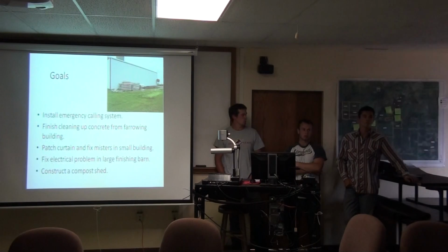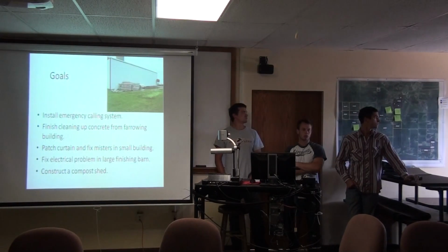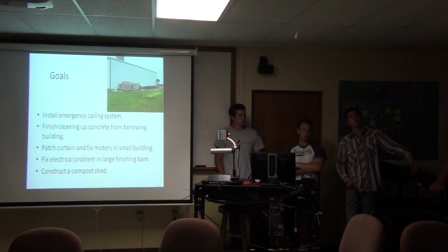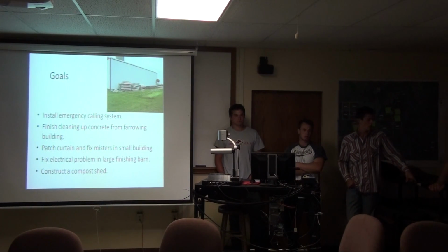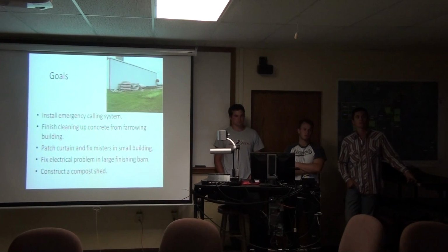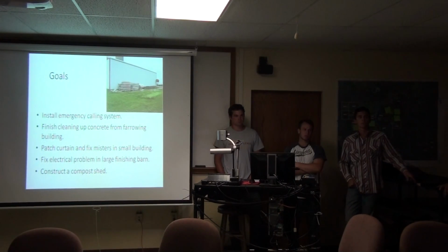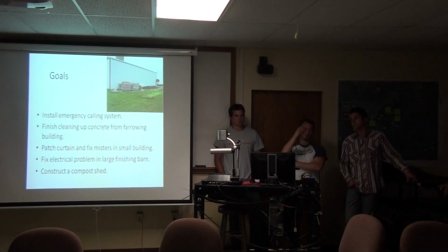Great question. More comments than questions. On the electrical problem, the big problem we're having is that for some reason the outlets that control the solenoids on the sprinklers down there are fluctuating from 150 to 190 volts in a 115 volt socket, so it's burning out the solenoids. I talked to them last week, they were on vacation this week, and I talked to them today. They promised someone would be here to look at that by the end of the week.